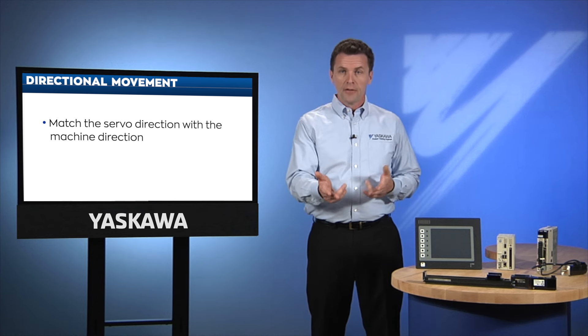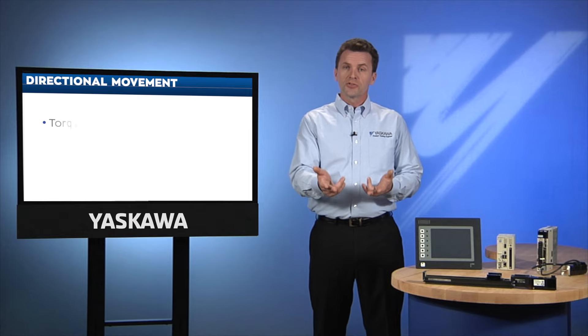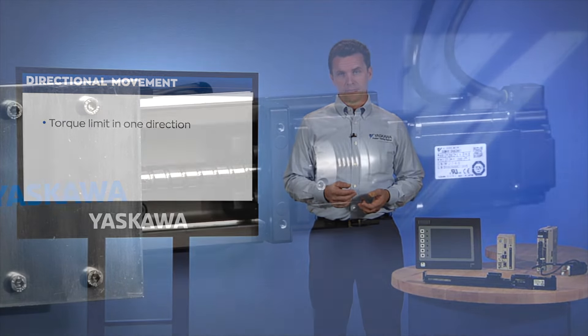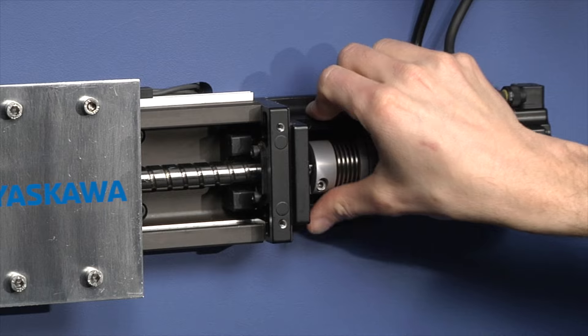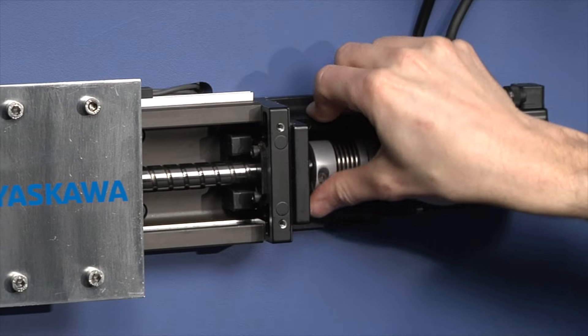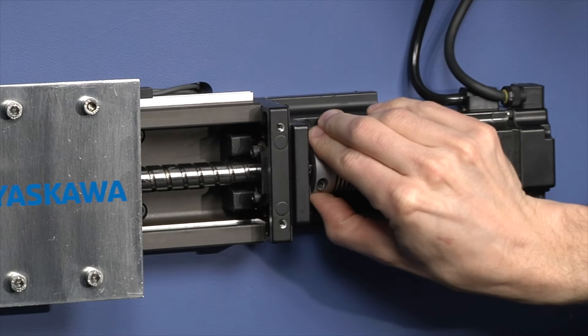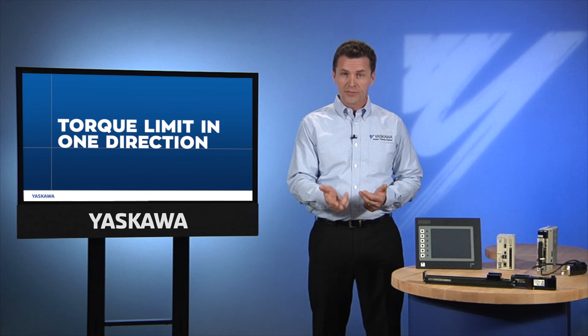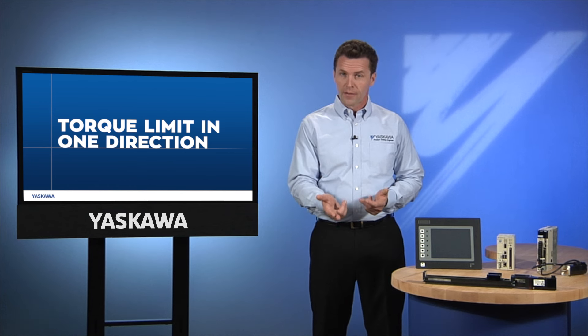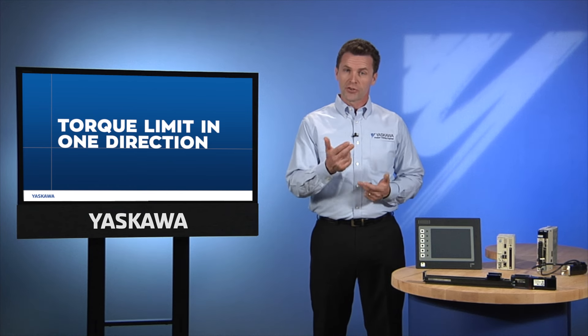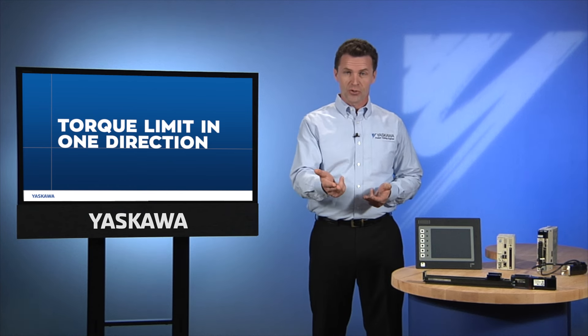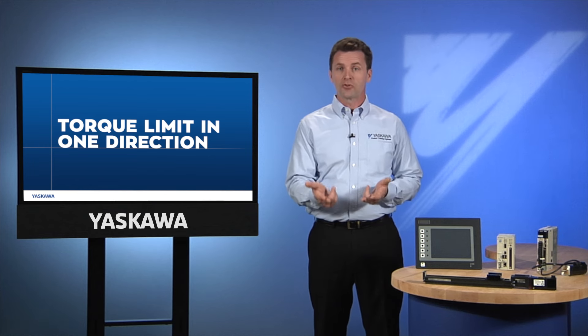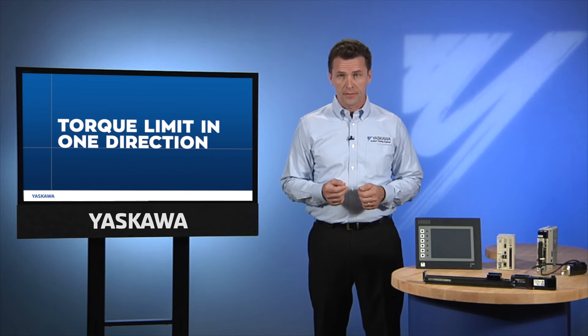For example, the servo may use a protective torque limit in one direction but not in the other. I can manually overpower the motor in one direction, but I can't overpower it in the other direction. So you can see why it's important to understand which direction is forward and which is reverse. In some circumstances, this could create catastrophic damage to your machine if not properly configured.